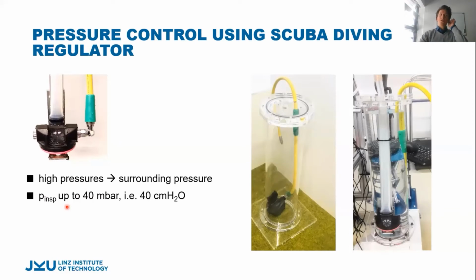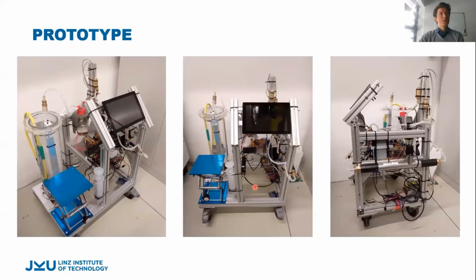And so how can we adjust the pressure here, the surrounding pressure? Well, we just put the scuba diving regulator in its natural environment, which is water. So we put it in this water column and fill it up. And the static pressure of a 40 centimeter water column is 40 millibars. So we can fill it up with water, and so in this hose, we just have 40 millibars. So by using this, we manufactured a prototype, which looks like this.